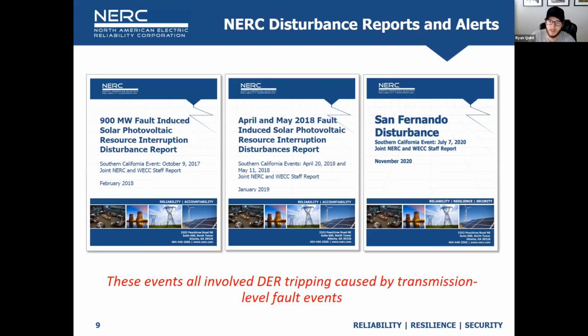And that's an IEEE 1547-2003 or 14. Jose knows best, but whatever the older version of 1547 is, that's an artifact of that standard. It's a disappear when the grid hiccups and come back 5 to 7 minutes later with pre-configured settings inside of it. I think the new 1547 does a lot better in that regard, and I'll talk more about that shortly. But the main message here is that DERs are being experienced, we're seeing their impacts on the bulk power system when we have normal bulk power system events now. And that's again, I won't be alarmist and say it's concerning, but it is noticeable for sure.